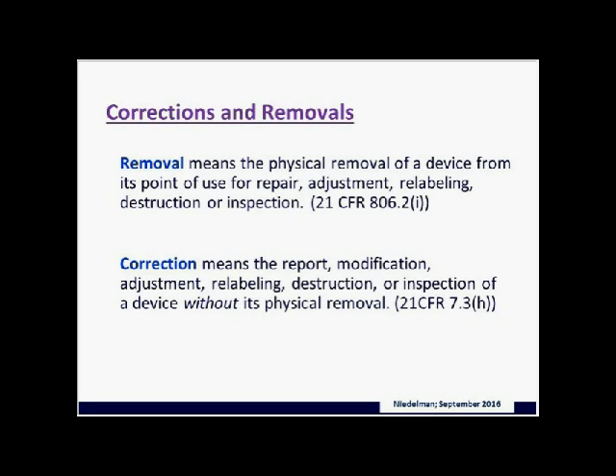You need to bring it back to your firm, whereas a correction can take place in the field. So the report, the modification, the relabeling, perhaps destruction or inspection of the device can take place at the healthcare facility. Obviously, capital equipment that's permanently installed would be corrective actions. There would be corrections associated with that.